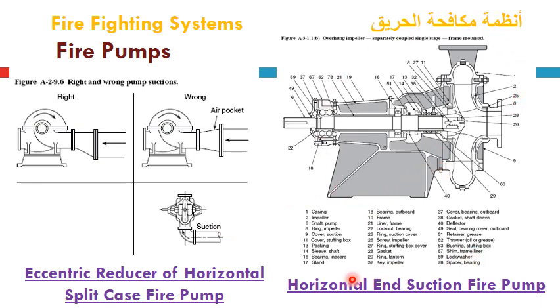In this graph we show the horizontal end suction fire pump with all construction details numbered here. As shown on this figure, this is the suction flange and this is the discharge flange, and this is the impeller affixed here. This is the shaft with its bearing and packing located here, and how the shaft is affixed to the impeller, and these bolts close the casing of the end suction pump. All the rings, covers, packing, sleeves and glands are mentioned here with numbers and shown on this numbering system below this graph.